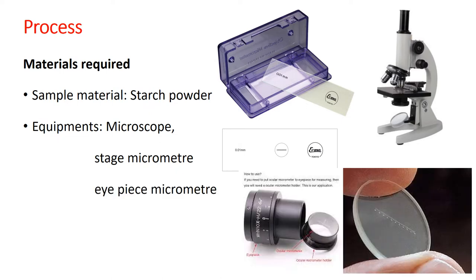Another equipment required is the eyepiece micrometer, which is similar to a normal eyepiece but fitted with an additional scale etched with markings from 0 to 100. To differentiate: the stage micrometer has no numbers — just lines — whereas the eyepiece micrometer has numbers 0, 10, 20, etc. You can also rotate the eyepiece micrometer to place the scale horizontally, vertically, or tilted depending on the particle to be measured.